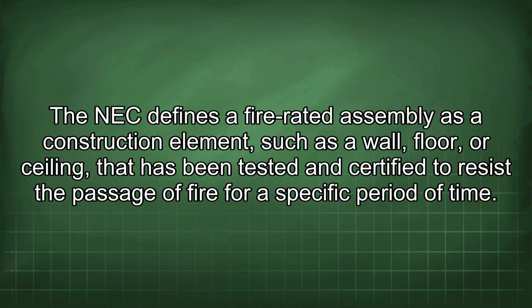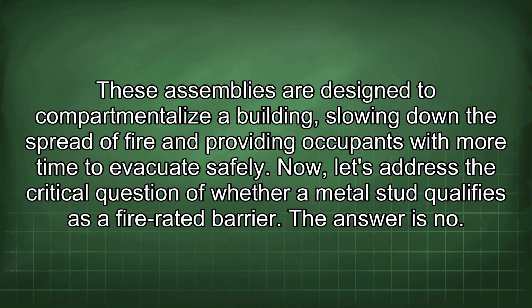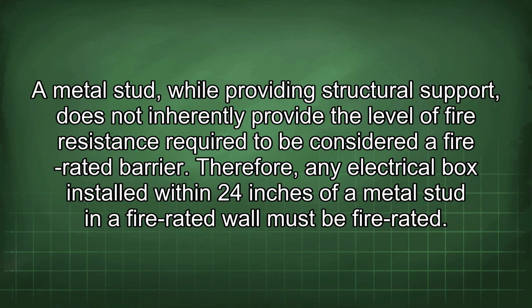The NEC defines a fire-rated assembly as a construction element such as a wall, floor, or ceiling that has been tested and certified to resist the passage of fire for a specific period of time. These assemblies are designed to compartmentalize a building, slowing down the spread of fire and providing occupants with more time to evacuate safely. Now, let's address the critical question of whether a metal stud qualifies as a fire-rated barrier. The answer is no. A metal stud, while providing structural support, does not inherently provide the level of fire resistance required to be considered a fire-rated barrier.